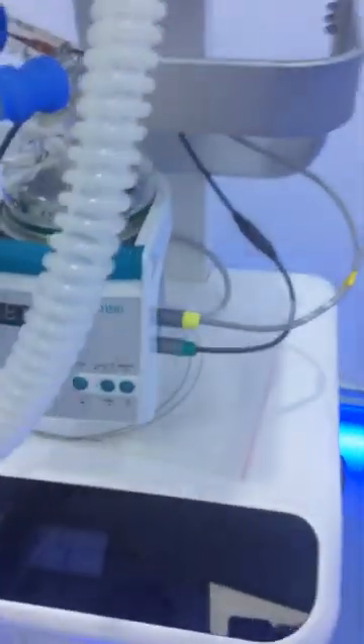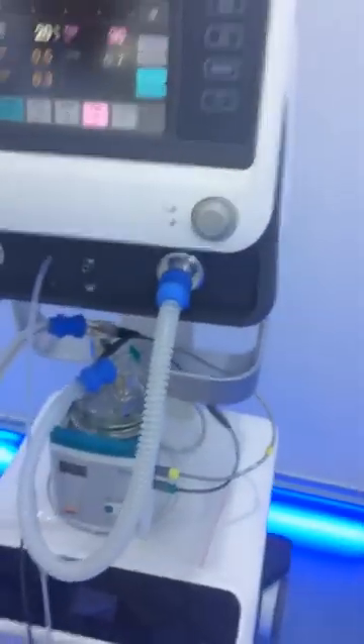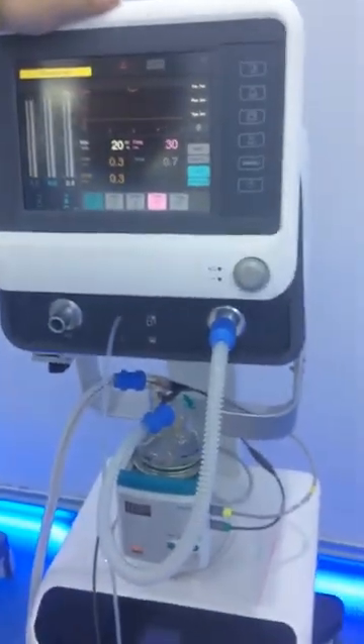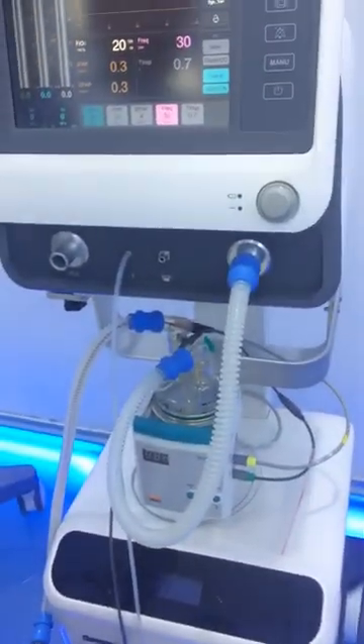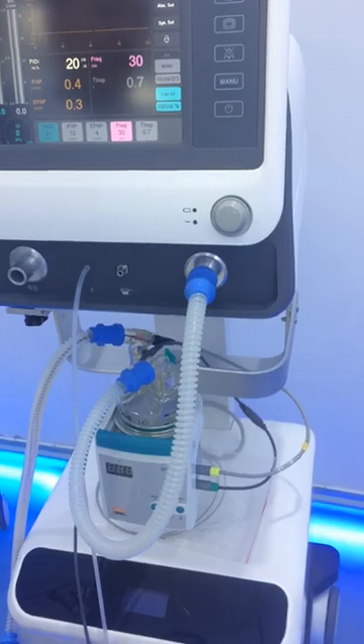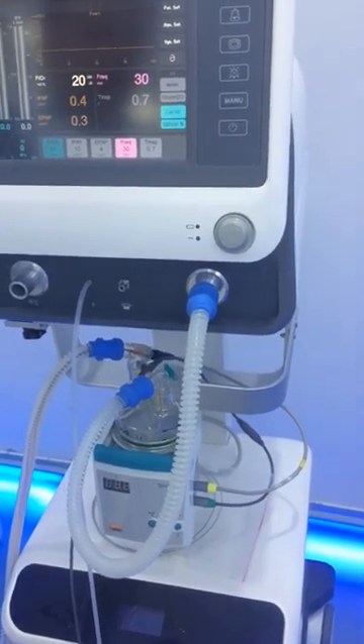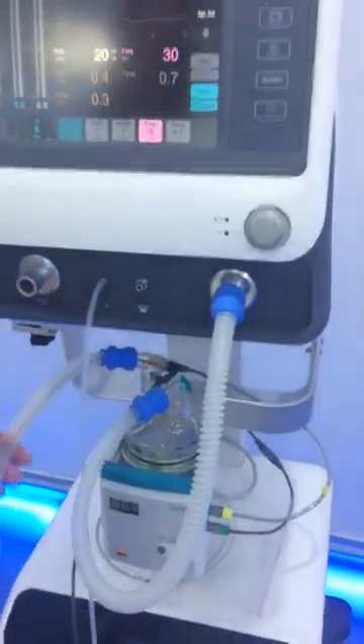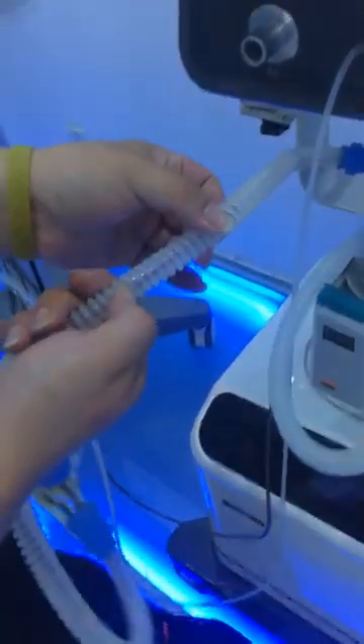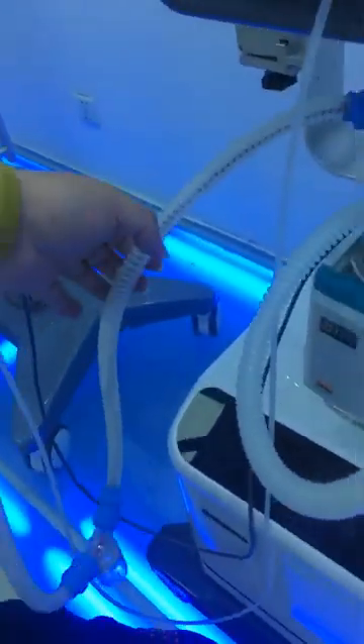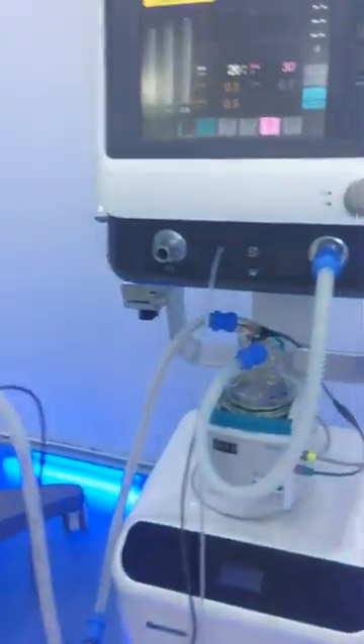And then the high-end one is this one. This one is similar to the MR850 from Fisher & Paykel. It has the same function. It has servo control, and the temperature can be set automatically. And inside the pipeline, you can see the red line, which is the heating wire. So this is the high-end humidifier.